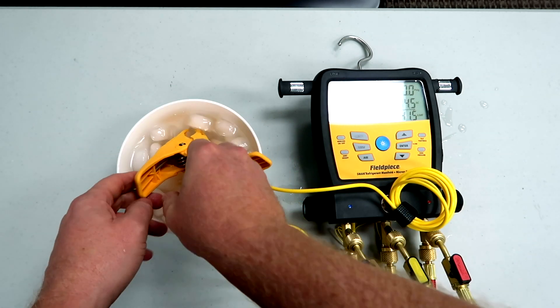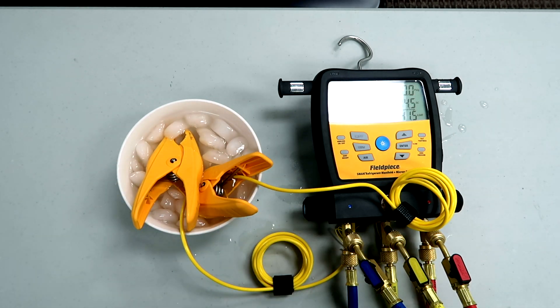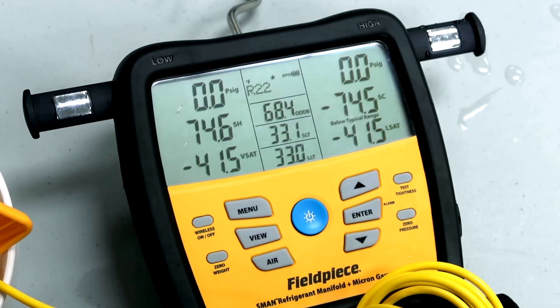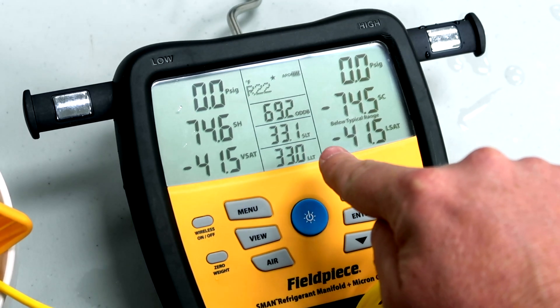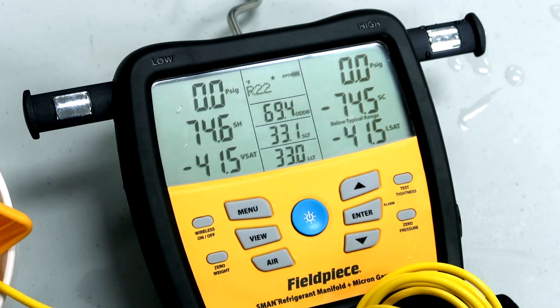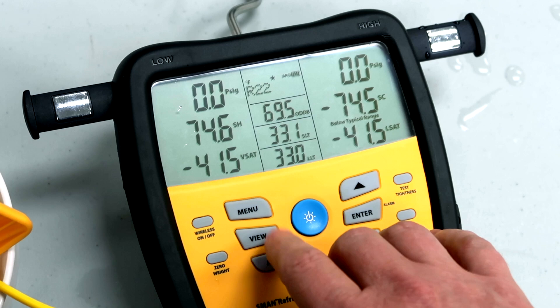We've got it in the ice bath and now we're going to zoom in and see what we have on our display. You can see we're reading just slightly high, 33 degrees on both of them, so we're going to go ahead and calibrate.